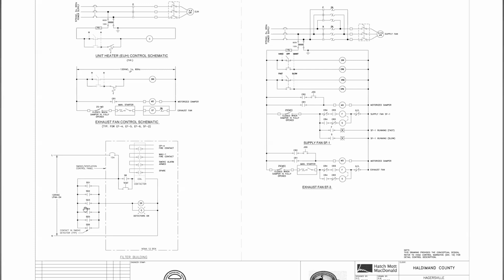We've got your different contacts, which will run up to the test button. These contacts will be smoke detectors scattered throughout the building. And these are the fire contacts for PLC, maybe an alarm beacon, MAU, fire contact. So the makeup air unit will turn on.